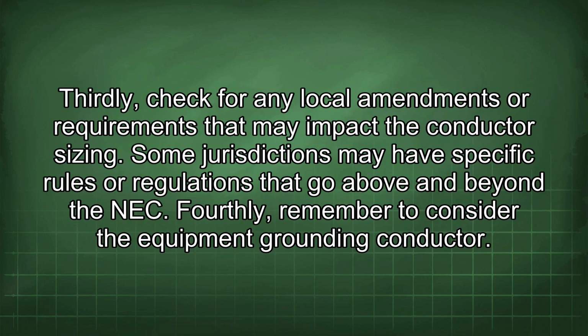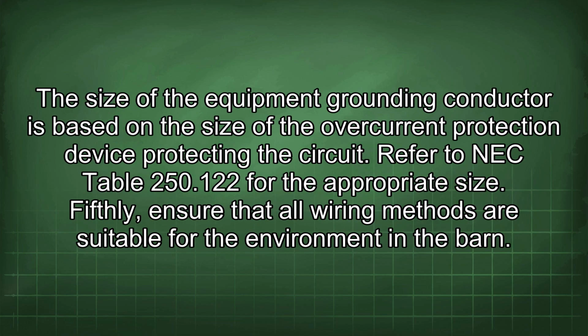Thirdly, check for any local amendments or requirements that may impact the conductor sizing. Some jurisdictions may have specific rules or regulations that go above and beyond the NEC. Fourthly, remember to consider the equipment grounding conductor. The size of the equipment grounding conductor is based on the size of the overcurrent protection device protecting the circuit. Refer to NEC Table 250.122 for the appropriate size.